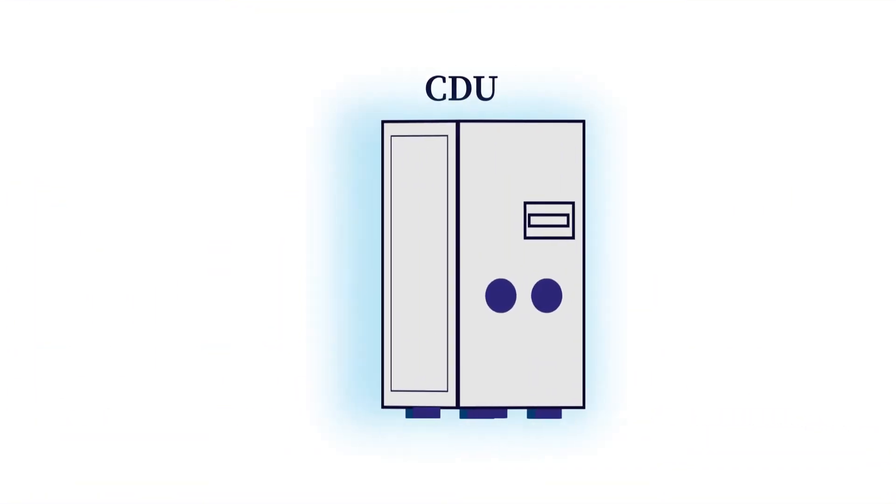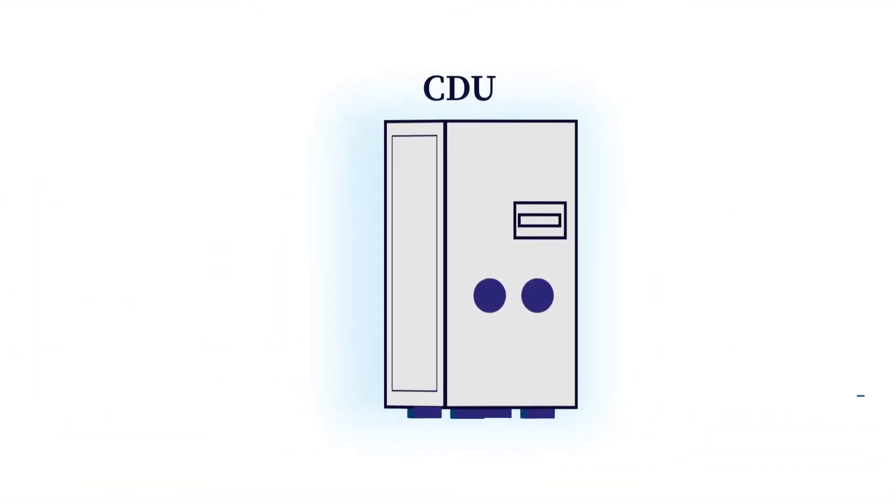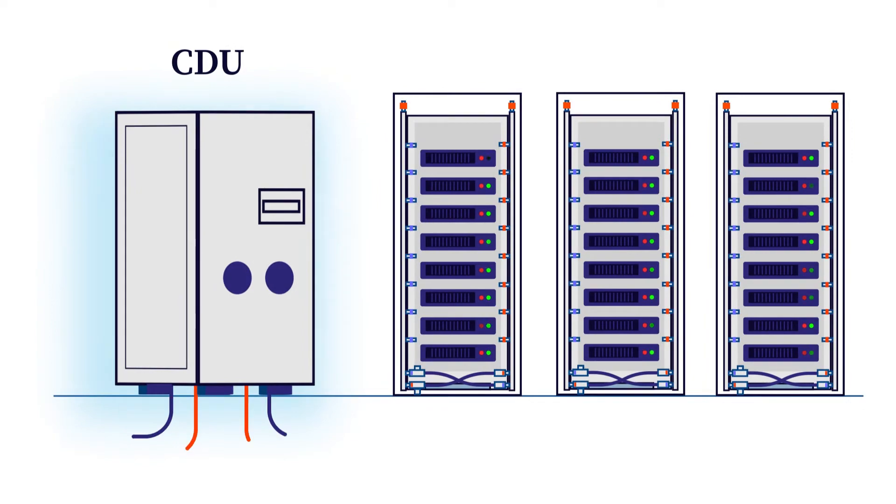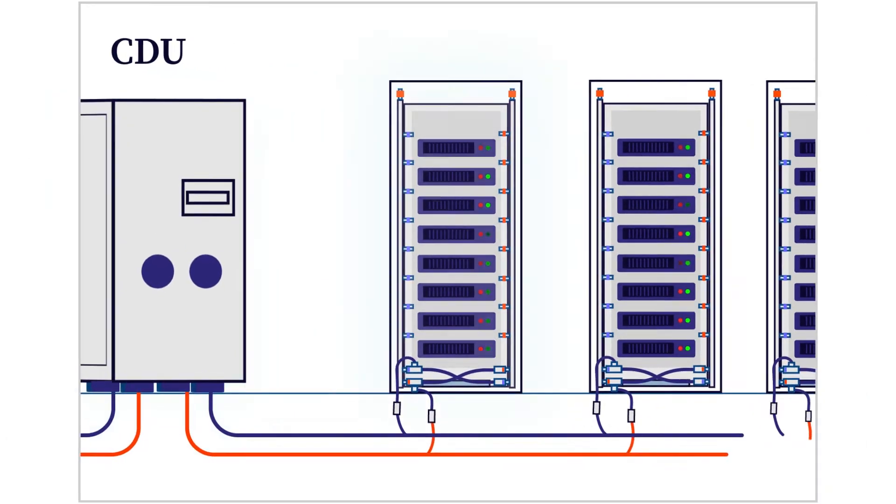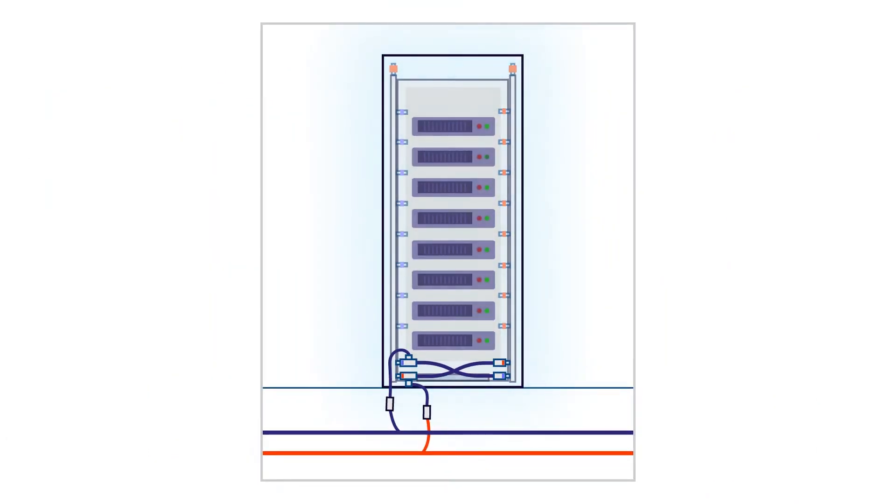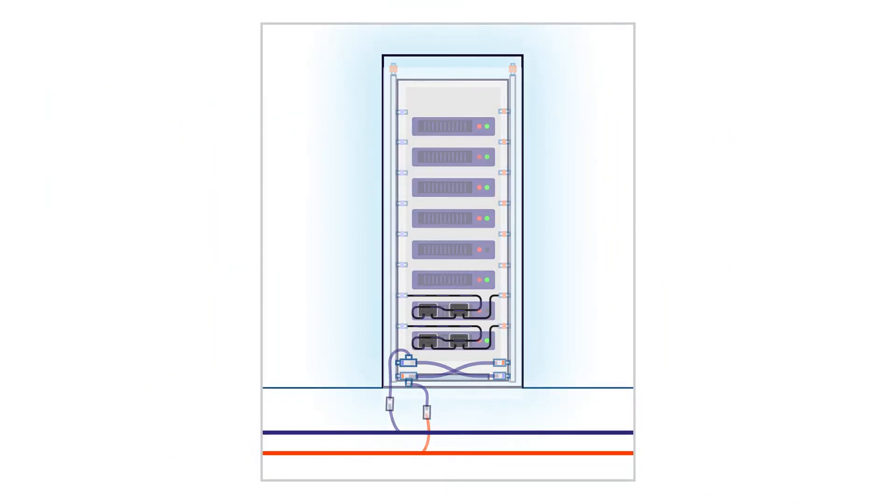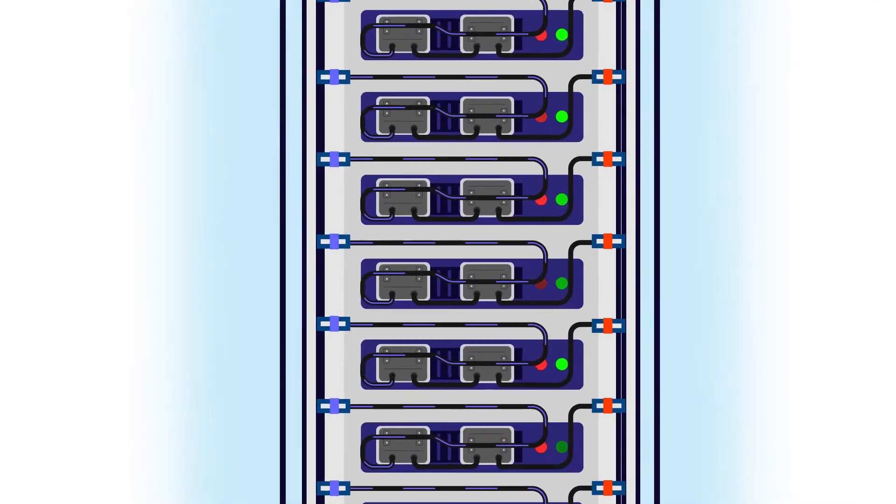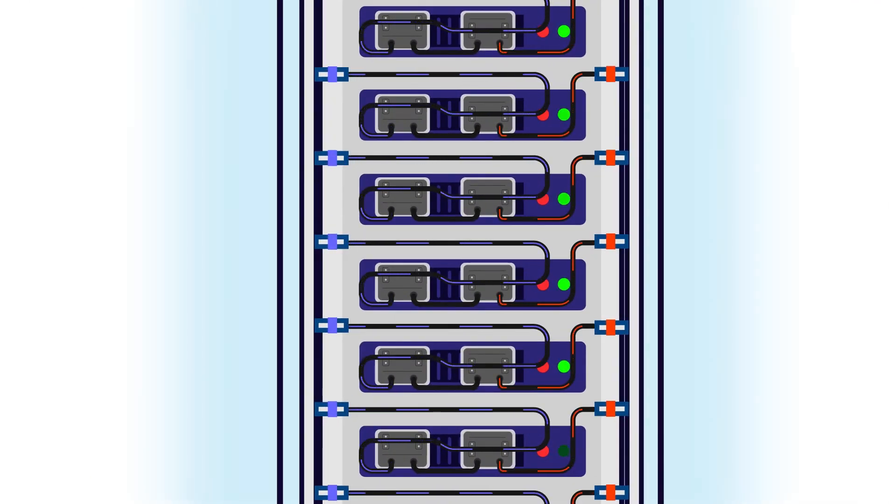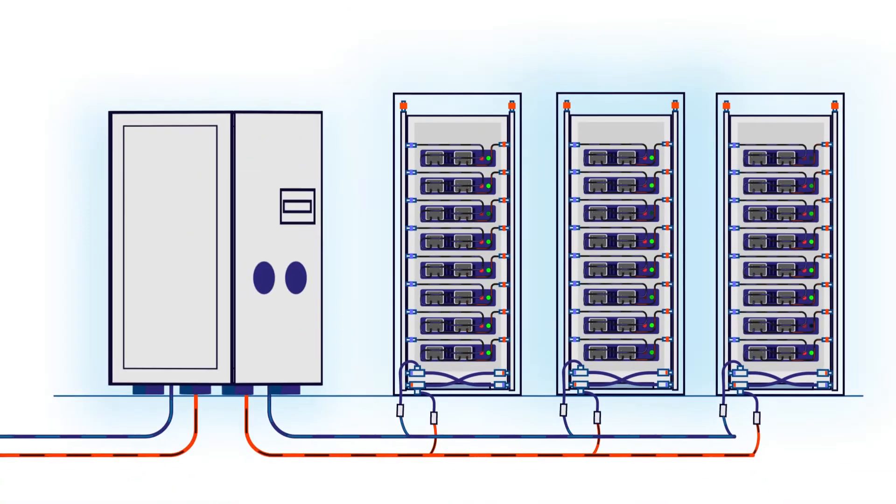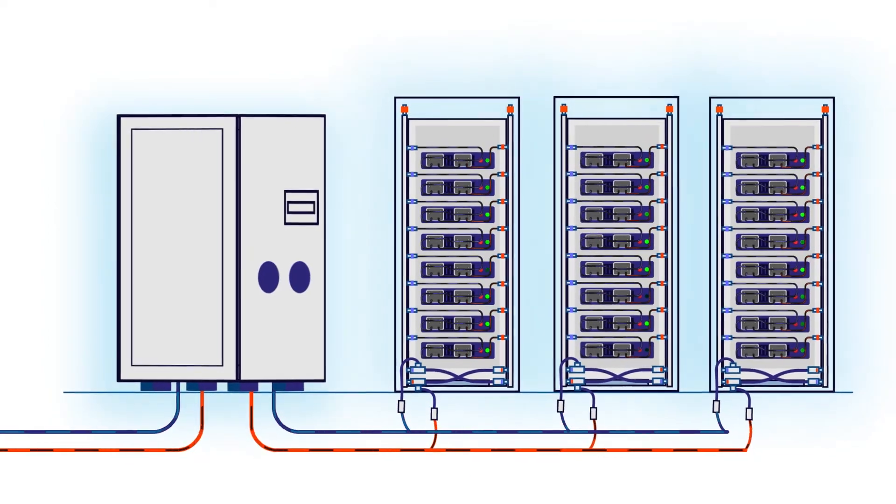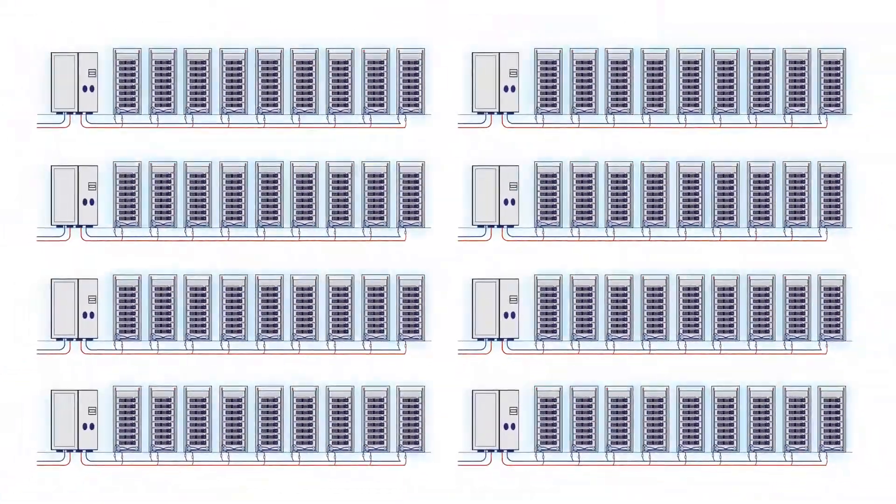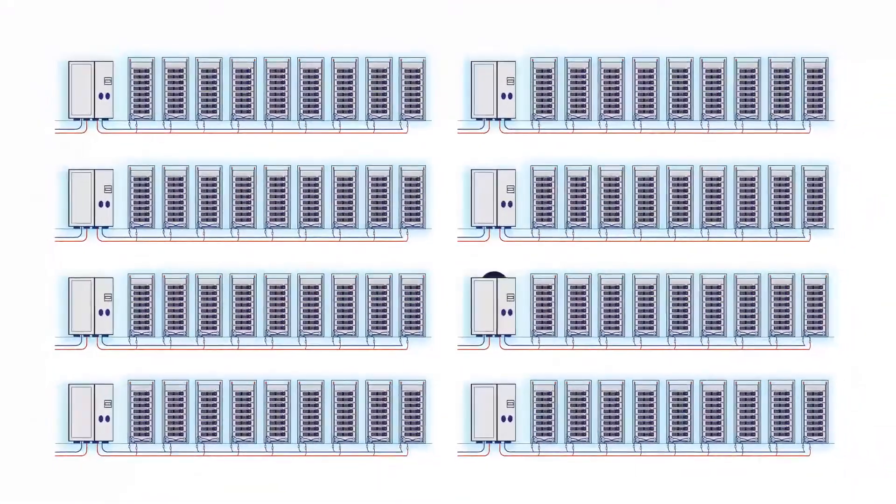The heart of the system is the CDU. The CDU pumps low pressure coolant to the rack manifolds, which distribute liquid to each passive cold plate loop inside the server. The passive cold plate loop captures the server's thermal load and returns the hot coolant back to the CDU for cooling.